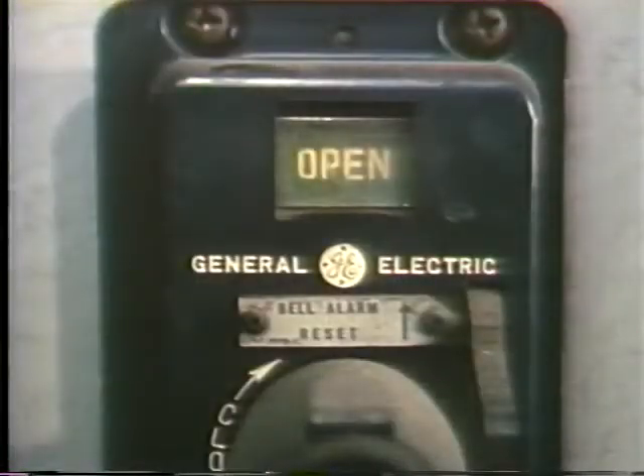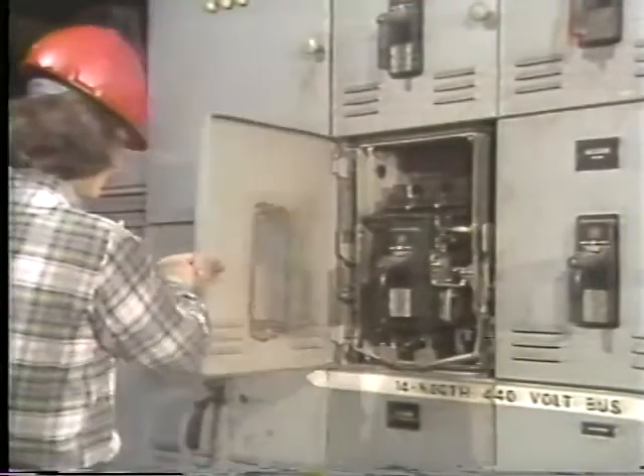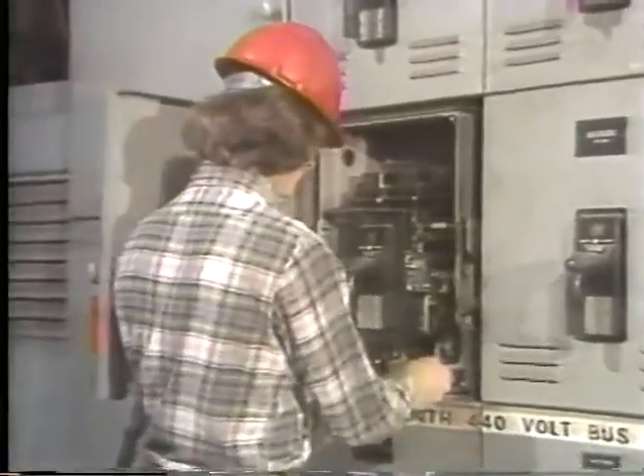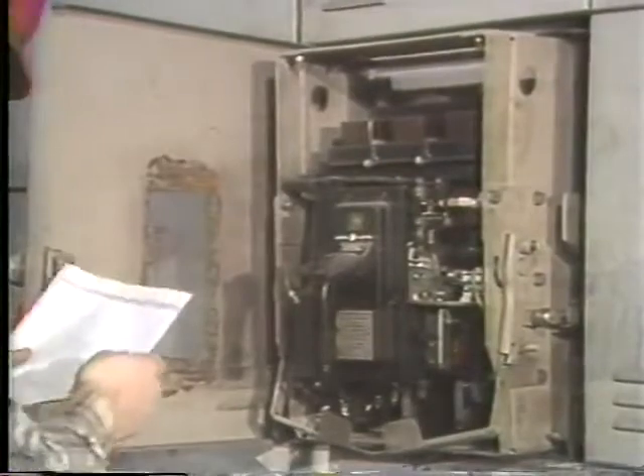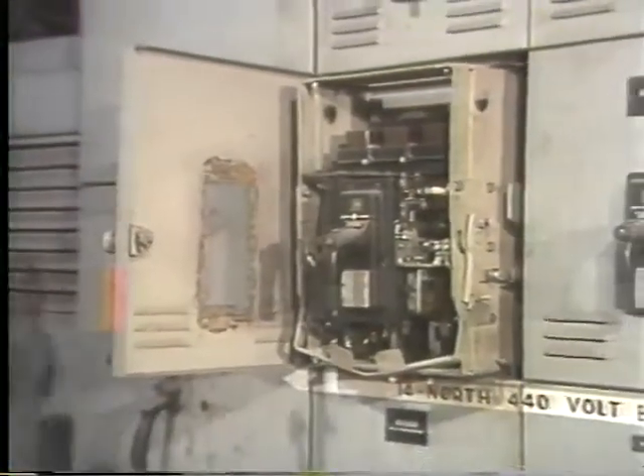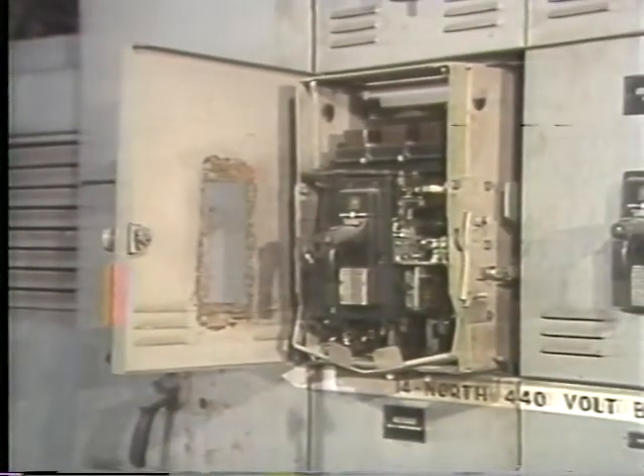He can see that the breaker's open, but the tag lets everyone else know that it's to stay open until work's completed. For extra safety, though, he racks out the breaker before starting work. When the breaker's in this position, it can't be accidentally closed while he's working on the load terminals.